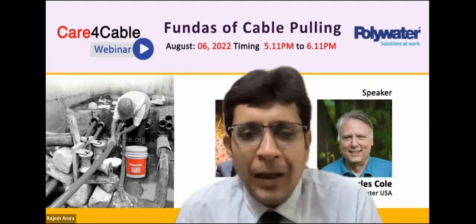Our cable line is 22 kV, and along with that 11 kV, 33 kV, and even cables up to 400 kV are running. The vendors have tried this megger instrument wherein they inject a signal with a particular frequency, or they tried something else.